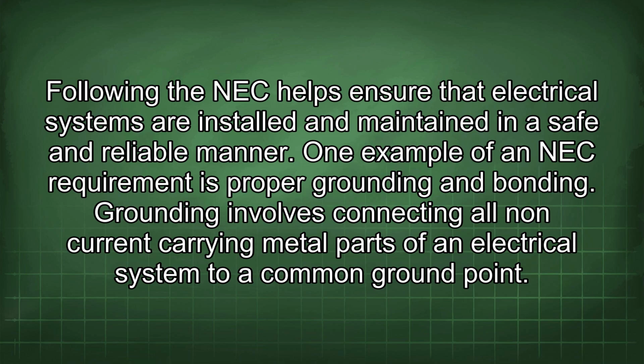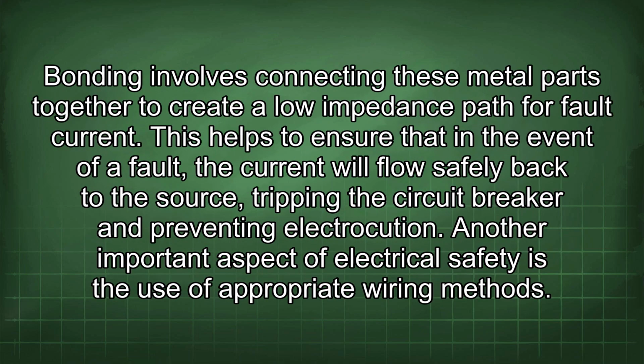One example of an NEC requirement is proper grounding and bonding. Grounding involves connecting all non-current carrying metal parts of an electrical system to a common ground point. Bonding involves connecting these metal parts together to create a low impedance path for fault current. This helps to ensure that in the event of a fault, the current will flow safely back to the source, tripping the circuit breaker and preventing electrocution.